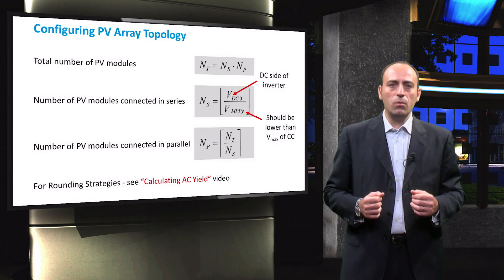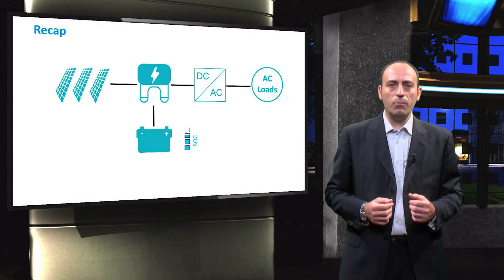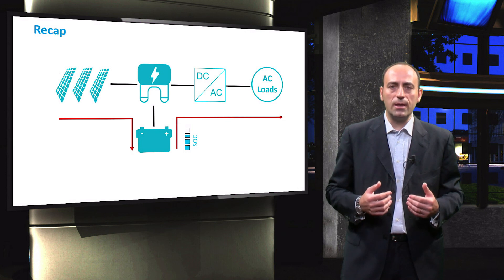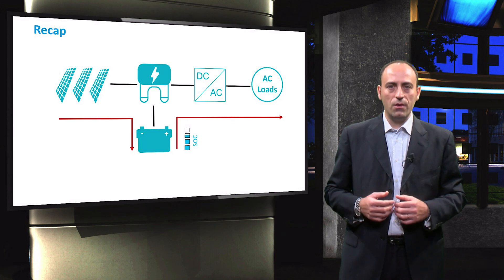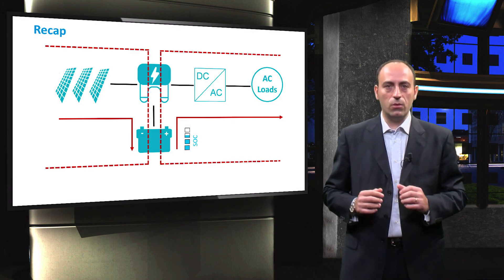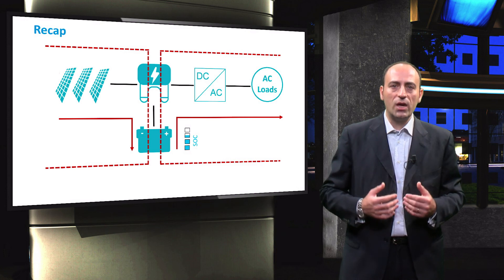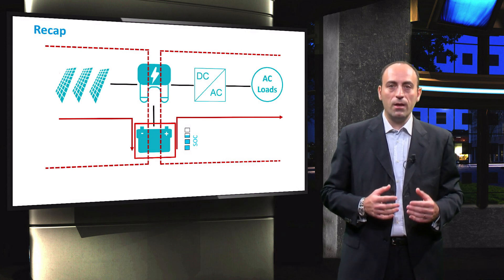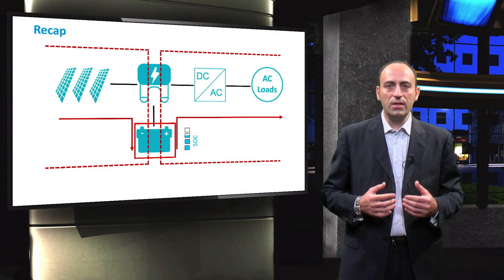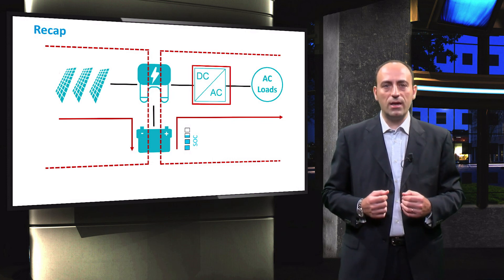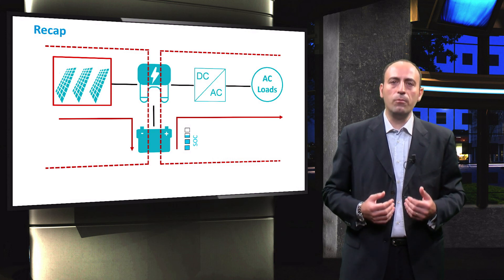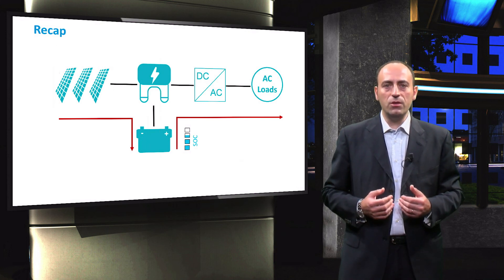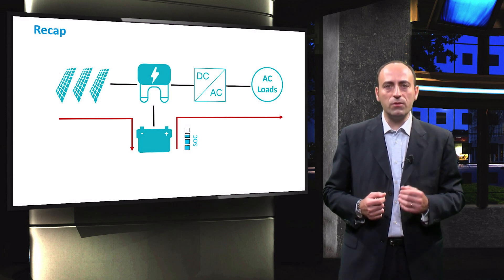To conclude, in this video we saw the sizing of the different components in a standalone PV system. The design of such a system is based on the concept that the flow of energy happens via the batteries at all times, thereby decoupling the PV array and the loads. The size of the battery bank is determined with respect to the load, then the inverter is sized, and finally the PV array size is calculated. In the next video, we are going to use the information calculated so far and from the previous video to determine the performance of the standalone PV system.